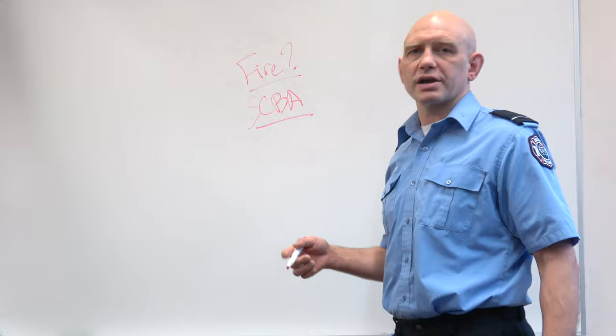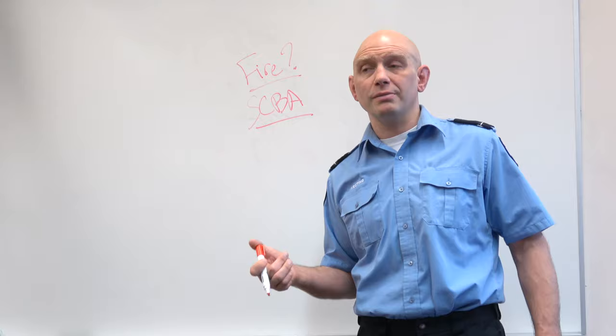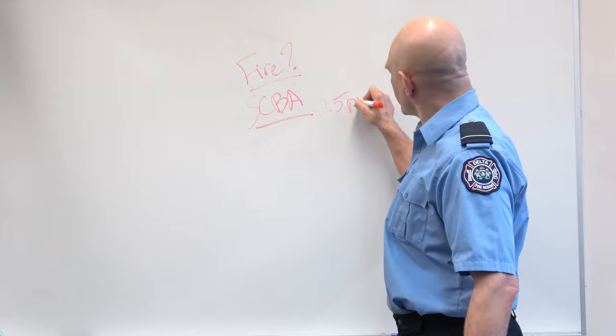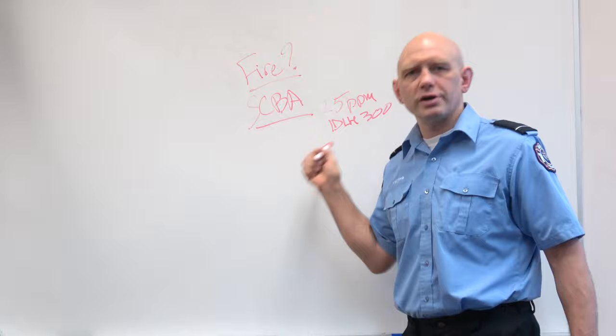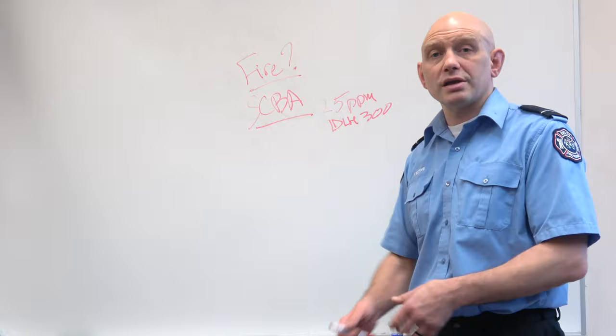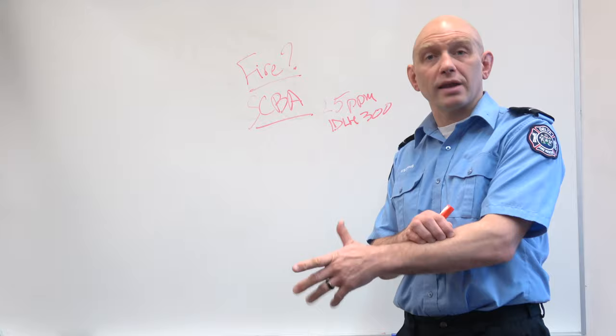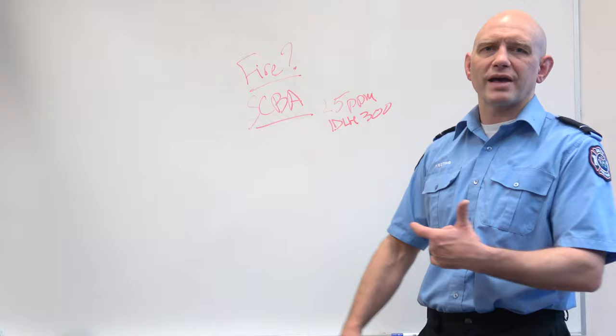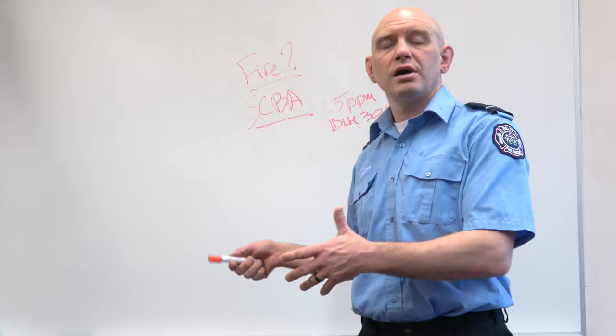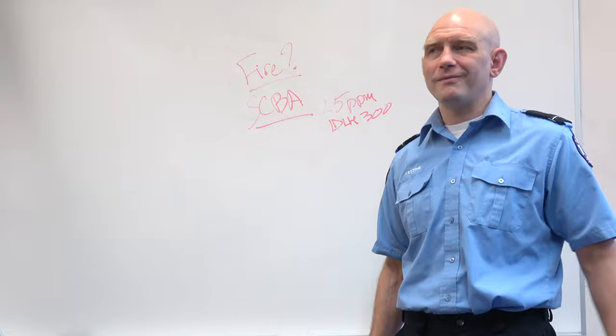So are there fire concerns? What are you going to use for respiratory protection? SCBA would be a minimum. Because if you're going in there to do some pipe fitting on a Freon, and you go in there in your station air, and you go in there and turn the valve, but that pipe is rotten and the pipe breaks. There is an emergency there or the valve just comes apart. Now you potentially are in an oxygen displacement situation. So you want to be on an SCBA in case there's a catastrophic displacement of oxygen. Depending whether this is flammable or not, whether this is skin toxic or not, ammonia is both, you're going to want to upgrade the level of protection.